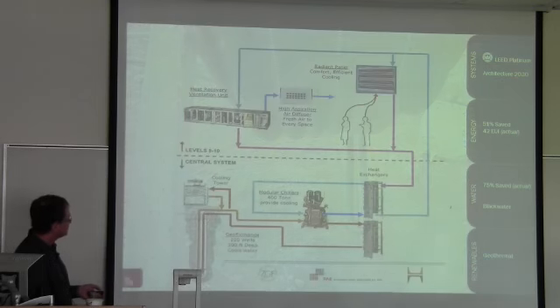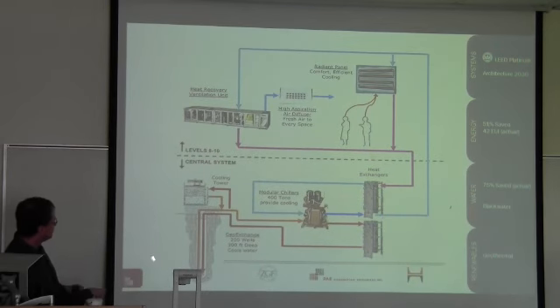The system in this building consists of the wells out here. There's a small cooling tower that's actually only a 50-ton cooling tower. It's like a little peaker plant to take the hottest days. But it actually hasn't been used that much because the ground field is working quite well. We have modular heat recovery chillers whose production on the heating side is up to about 140 degrees, and on the cooling side, we're only bringing it down to about 38 degrees, but they can go far below freezing.